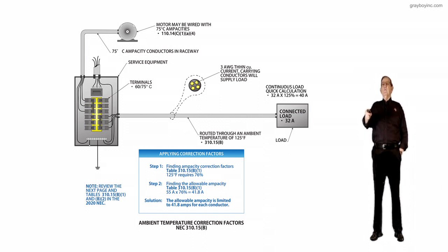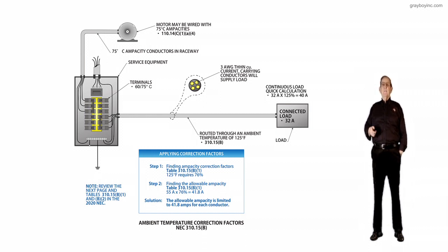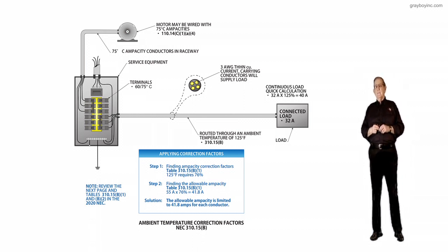And then you have number 3 AWG THHN, so you're plenty large enough there to serve that. But you could use number 6 up there if you wanted to. That's just in the illustration. They're showing they've used number 3 because they don't want any problems at all in their routing. And remember, when you tack on that 125% of the connected load, you're derating that breaker 80%. So that's what has taken place here. And I think that explains that about as well as we can without going into further explanation on how you would perform these calculations.